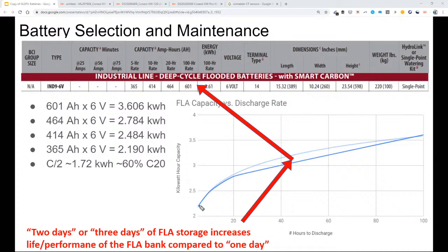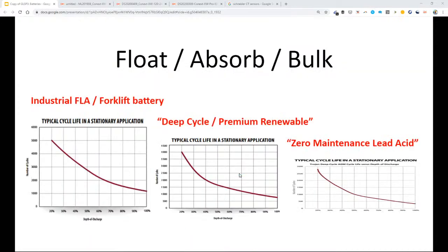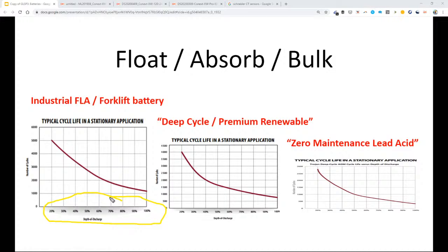And so, I'm also not trying to say that you can't put a load on a lead acid battery for 30 seconds that is beyond its C5 rating, but any kind of continuous sustained load that's large is going to be very hard on it. And this is going to come back to lithium ion batteries in a minute, but the traditional battery spec sheets have had these charts where you say, okay, well, what is my daily energy use and what is my storage capacity, and that'll tell me how deeply I'm discharging my battery on a daily basis. And based off your depth of discharge, you could go and determine how many cycles of battery life you have.